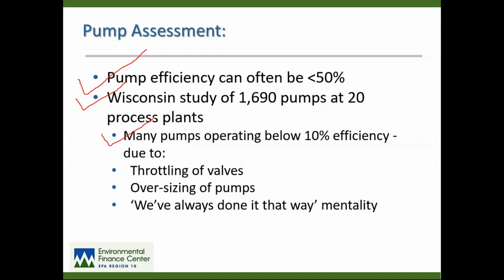Many of the pumps that they found were operating way below 10% efficiency, and you don't want a pump that is operating at 10% efficiency. Again, that's 10 cents on the dollar for work done versus energy purchased. Very often they are that low efficiency because operators have throttled the valves for one reason or another. Maybe they needed to moderate flow, or in the case of a well pump, at certain times of the year, maybe the water levels were dropping in the well, and to avoid sucking air at the inlet, they actually throttled the pumps down by turning the discharge valve down.